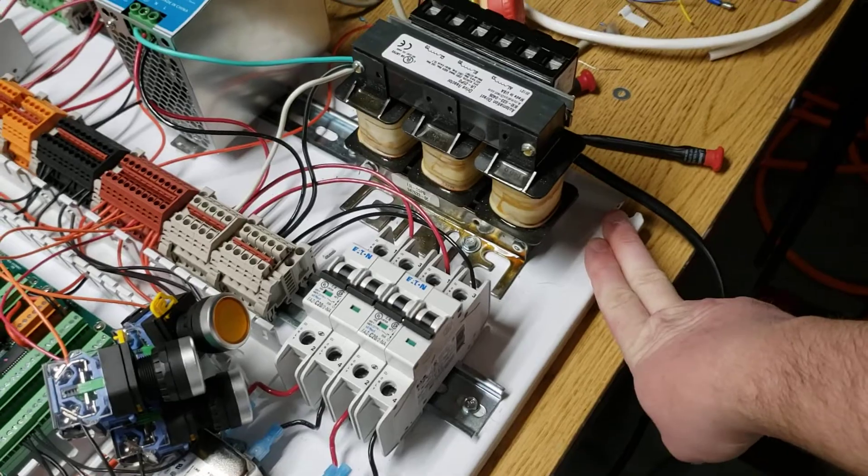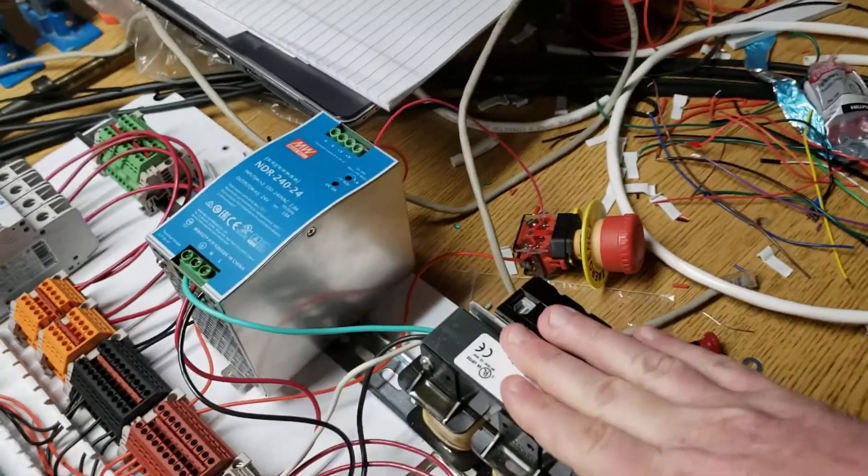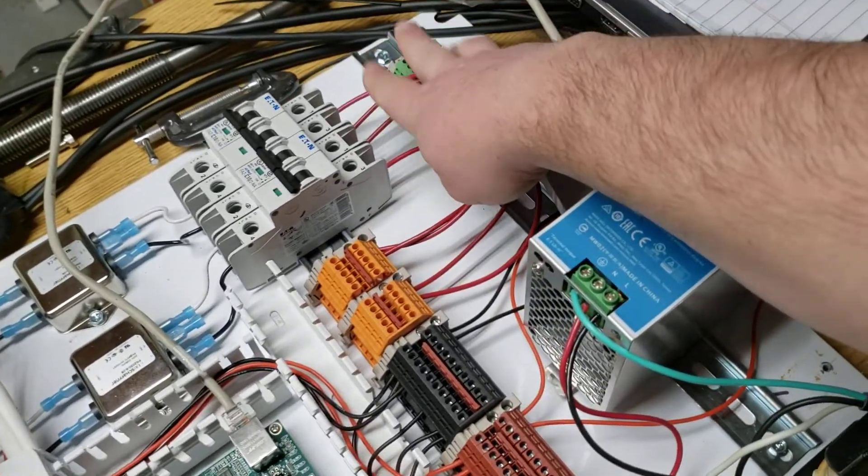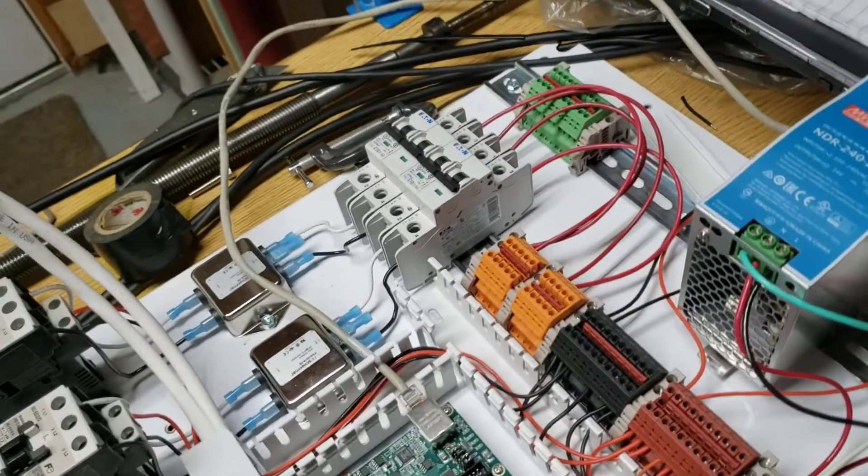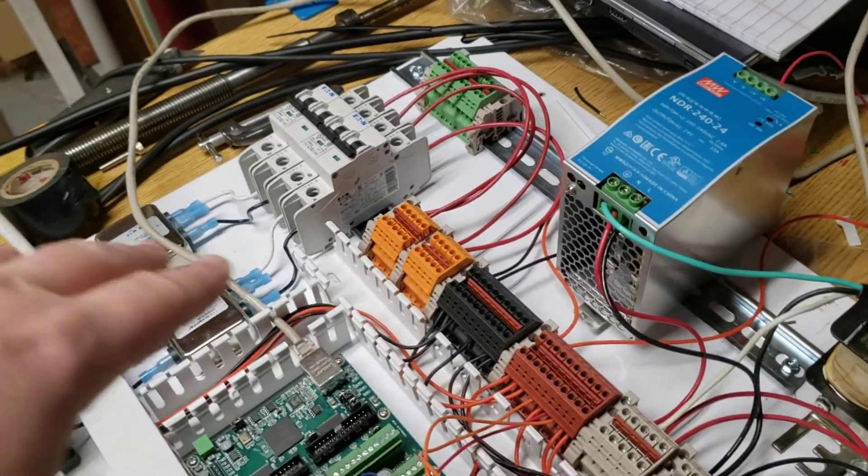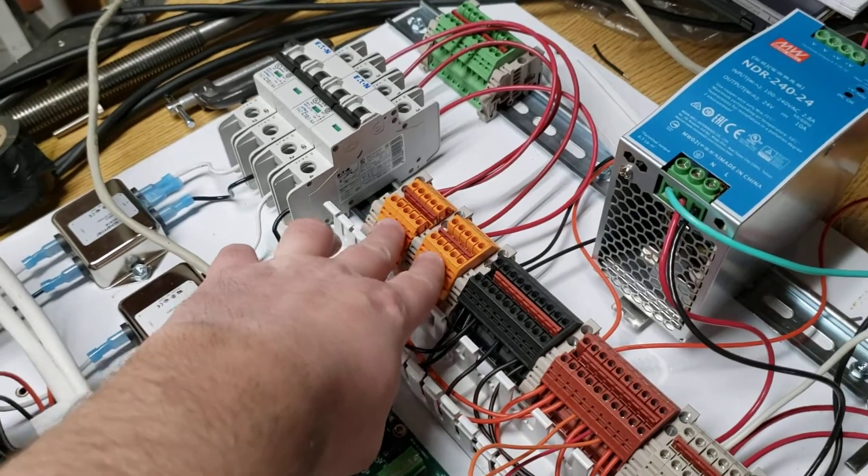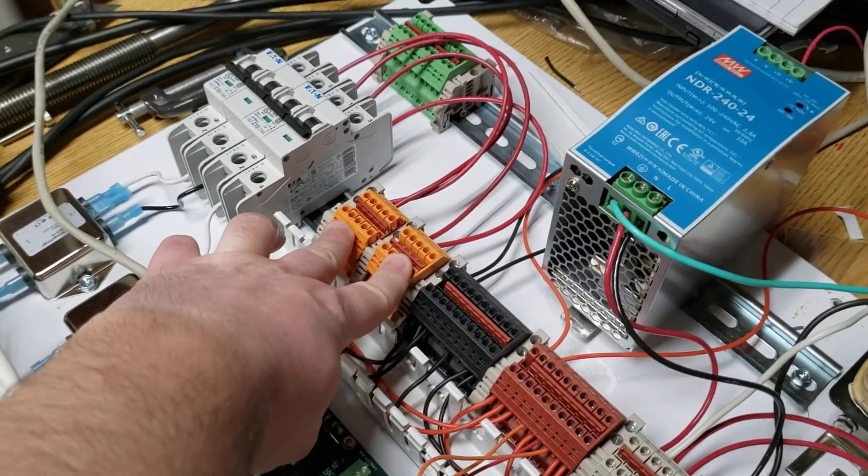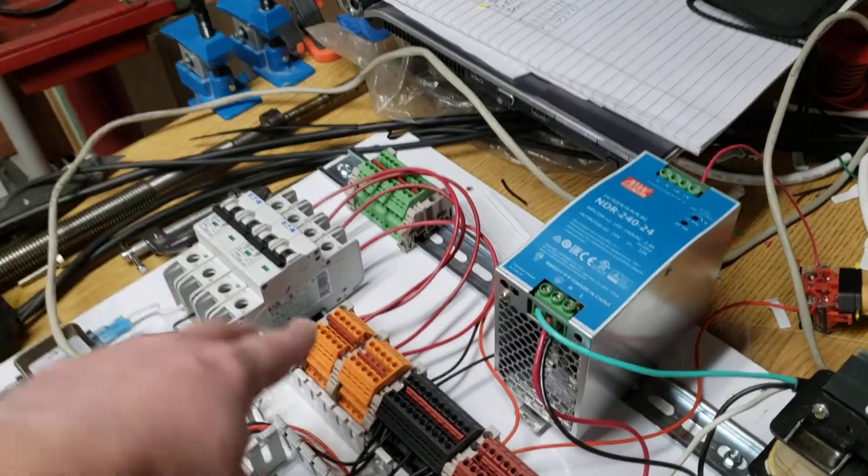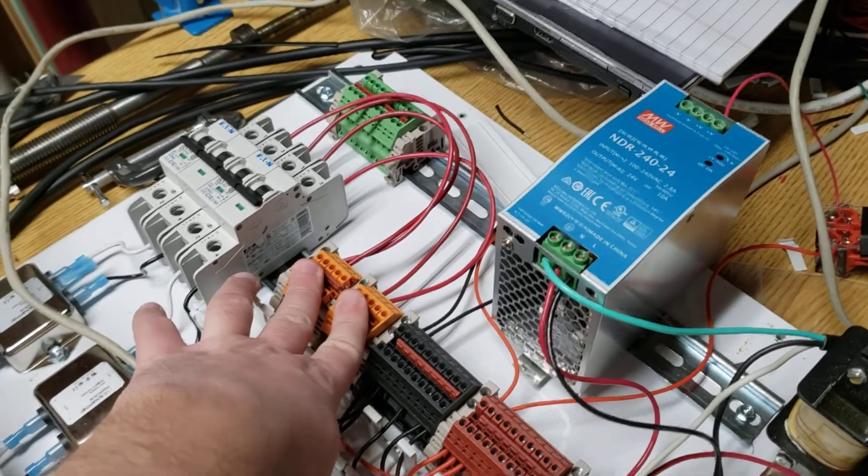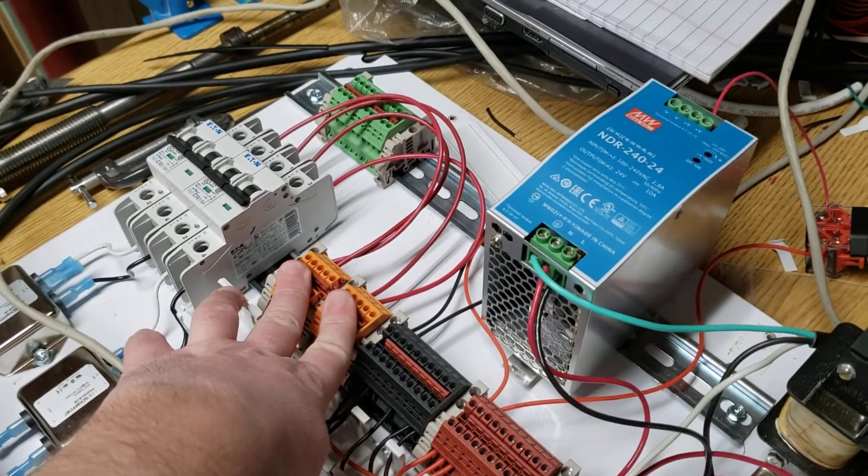When the panel goes into the enclosure, I'll have a grounding location here, and I'm going to have a neutral wire coming across going to this green block here. And that's going to feed my neutral return for my 110 circuits. The 110 circuits are also going to get branched off. Each one is going to power an outlet on the cabinet side, or it's going to power my computer off of the incoming 220.